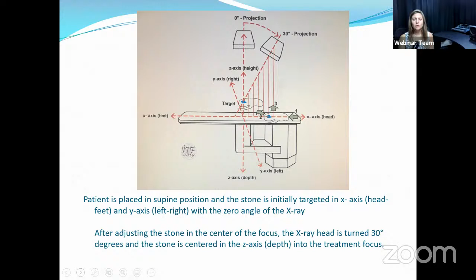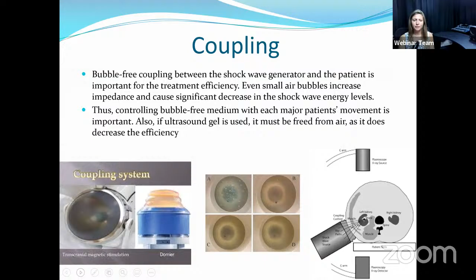What is coupling? Essentially, the medium in which the shockwave will need to travel is an aqueous solution, and this needs to be free of bubbles. Why is that? Because even a small bubble can decrease the energy level and give a suboptimal treatment. So it's very important that all the air contained in the solution is removed before starting the treatment, and this needs to be very well observed and followed during the treatment.